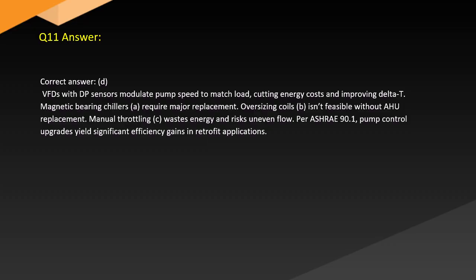Answer. Correct answer: D. VFDs with DP sensors modulate pump speed to match load, cutting energy costs and improving delta T. Magnetic bearing chillers (A) require major replacement. Oversizing coils (B) isn't feasible without AHU replacement. Manual throttling (C) wastes energy and risks uneven flow. Per ASHRAE 90.1, pump control upgrades yield significant efficiency gains in retrofit applications.